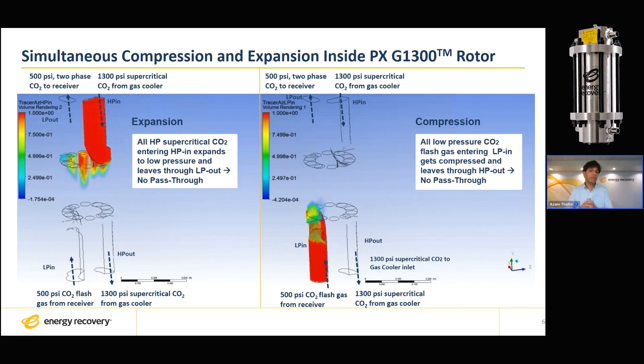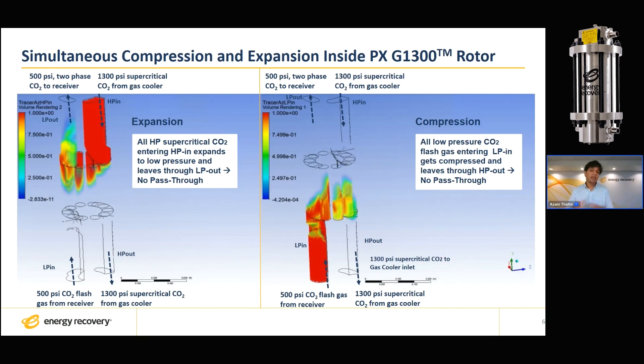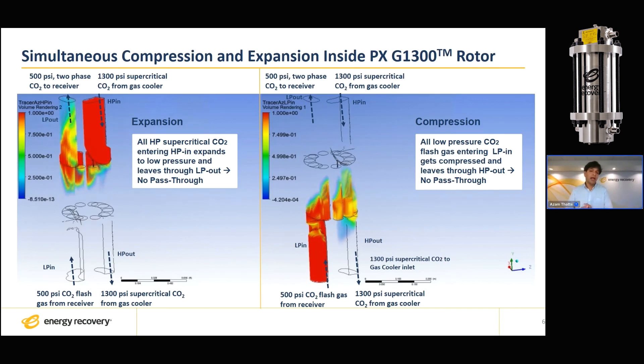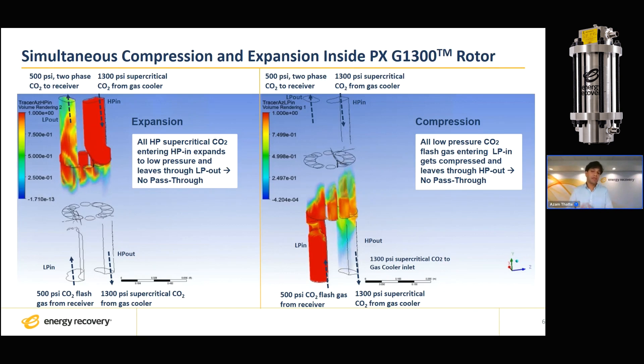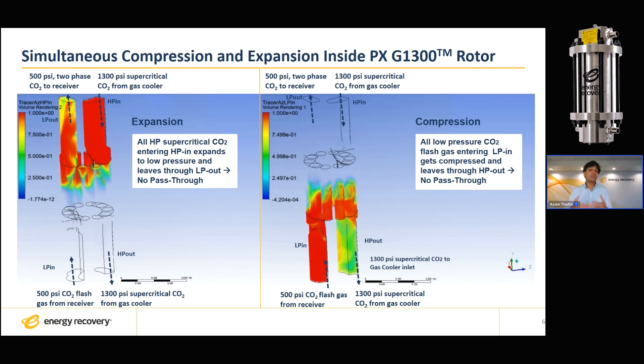It's not quite isentropic, but isentropic-like. But it's definitely a more efficient expansion than isenthalpic expansion that happens in a standard high-pressure expansion valve. As that supercritical CO2 expands to the low pressure, it becomes cold and it produces a liquid gas mixture — except that it produces more liquid after expansion through a pressure exchanger than it would have produced in a standard expansion through a high-pressure valve.